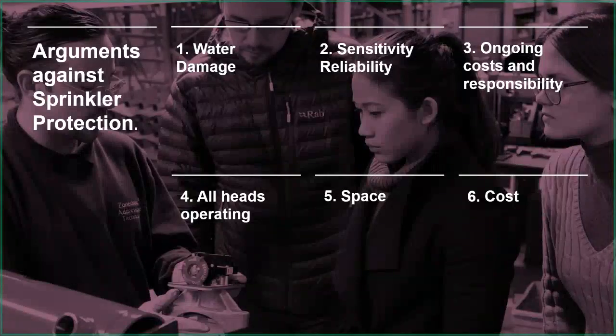For a commercial system, there are things to do on a weekly, monthly, 6-monthly, and yearly basis. Quite a list of things, but it's all there to keep the sprinkler system in full working order. Otherwise, what's the point in having one? If you're not confident it's going to do the job, there's no point in installing it.